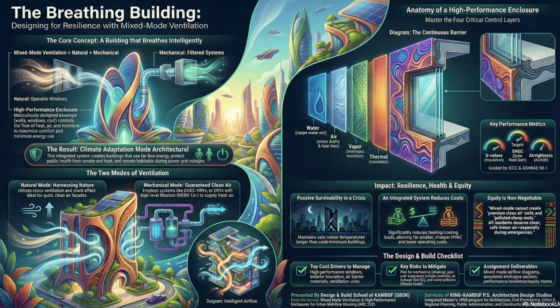The primary outcome of a great enclosure is load reduction. Reducing the workload for the machines. Exactly. Every single dollar you spend on continuous insulation, on low SHGC glass, on air tightness, it directly reduces the building's thermal load. And when you reduce the load? When you reduce the load, the resulting mechanical systems, the chillers, the boilers, the heat pumps, the fan coils, they can all be significantly smaller. Which saves money up front.